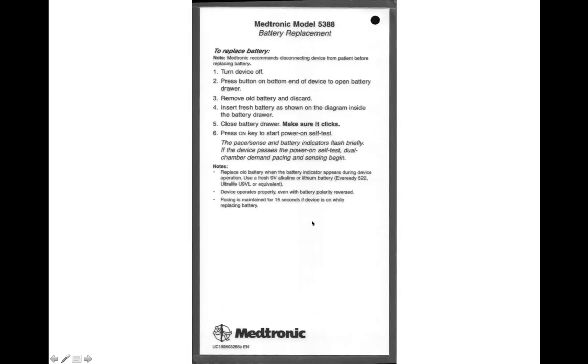For battery replacement, just as a word of caution: when you see the battery light indicating that your battery life is at minimum, you need to go ahead and change it out. While pacemaking continues for 15 seconds during replacement, if you wait a long time after the battery symbol appears, it will actually be less than 15 seconds — so replace it within a reasonable time frame.